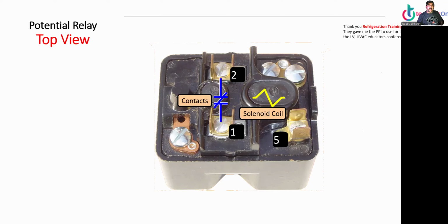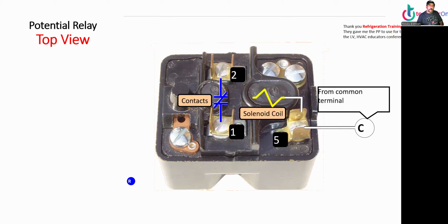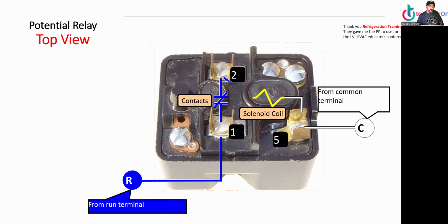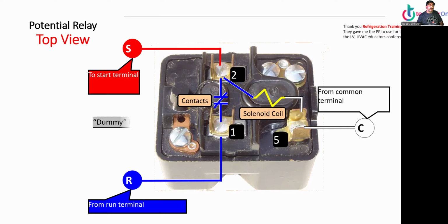Coil, contacts, common from the compressor terminal, from the run terminal, and to the start terminal. And those two are dummies. They go nowhere.